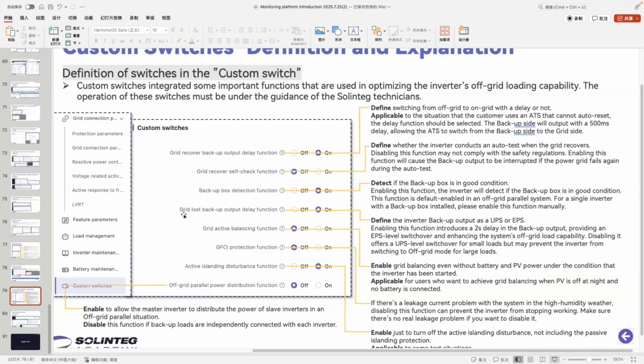The grid lost backup output delay function is for the backup box detection function. It is for the situation where, in an off-grid case, we have some parallel inverters and have connected the system with the backup boards. This function is open by default. But what if there is just one inverter in the system and it is also connected with the backup boards? In this case, we can choose to open this function so that we can detect whether the backup boards are in good condition.